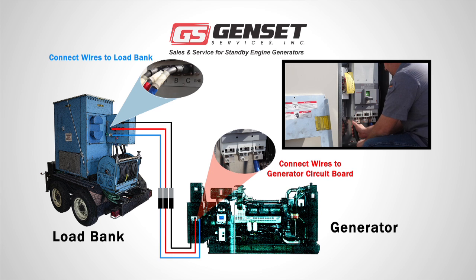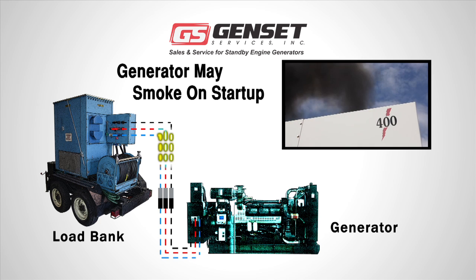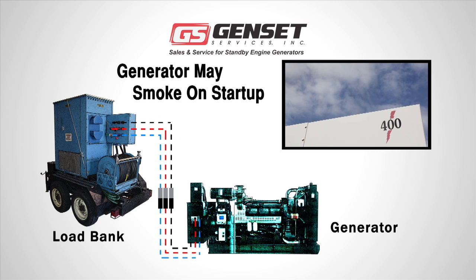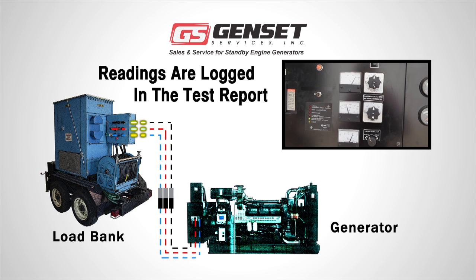The generator set is then started, and quite often, a set that has not been loaded on prior runs will smoke on start. The technician records the readings, verifies the set is performing as it's meant to, and logs it in the report referencing the hours that have passed.